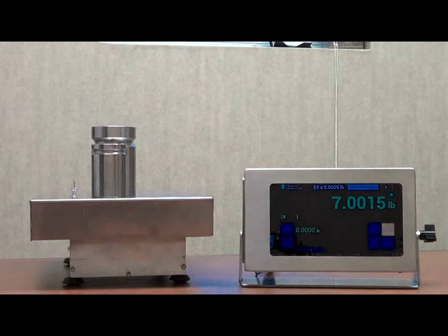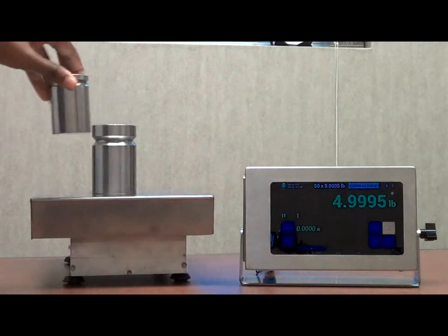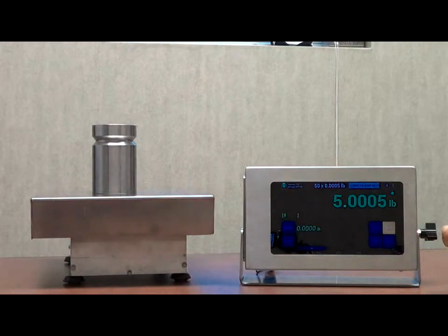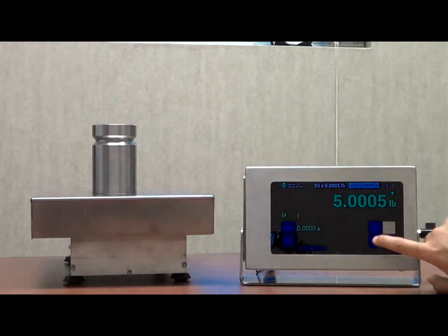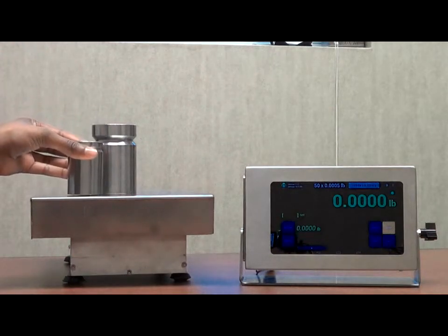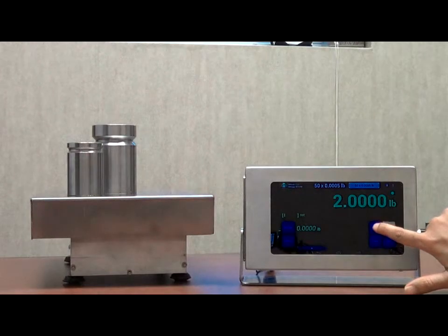The scale also has a tare function wherein we can show weights of certain items. We're going to go ahead and tare out the weight that's on there now. So now it's not registering the weight that's already there. We are going to place the smaller weight back on here. You'll see it's stabilized and it's showing the weight. There is a net gross switch which will allow us to see the complete amount as well as the tared out amount.